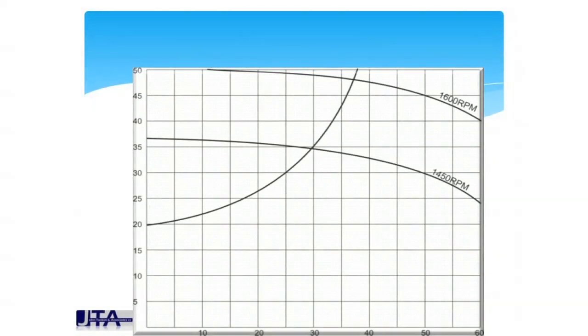Once we'd drawn the system head curve, it became apparent that for all that effort, we increased the flow rate from 30 up to maybe 37 - he maybe got himself a 20% increase in flow rate. The energy increase was in the region of about 80 to 90% in energy consumption. So all the kilowatts in the world thrown at this wasn't going to sort it out. This is not a question of power. This is a question of brain power.